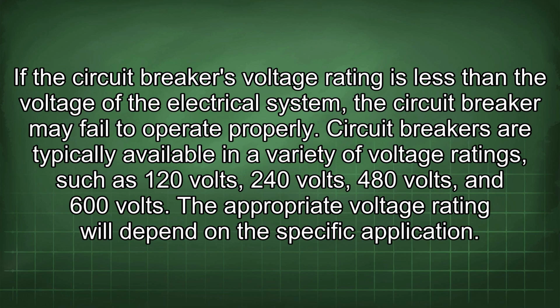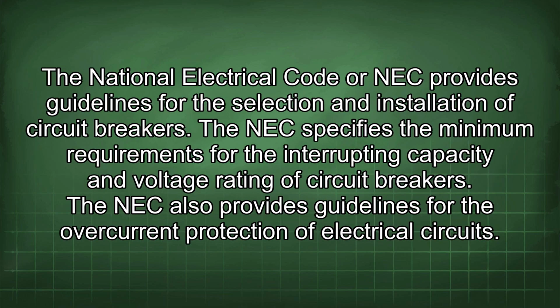Circuit breakers are typically available in a variety of voltage ratings, such as 120 volts, 240 volts, 480 volts, and 600 volts. The appropriate voltage rating will depend on the specific application. The National Electrical Code, or NEC, provides guidelines for the selection and installation of circuit breakers. The NEC specifies the minimum requirements for the interrupting capacity and voltage rating of circuit breakers.